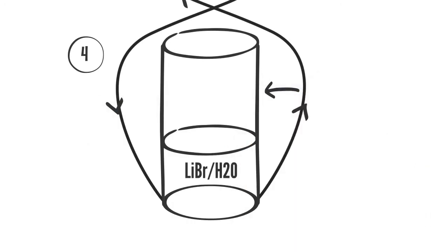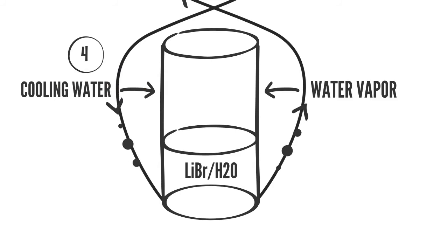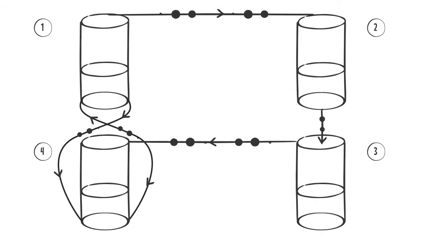The fourth phase contains, as in the first phase, a solution of lithium bromide. The third phase water vapor is sucked into the fourth phase and absorbed again in the solution of lithium bromide.